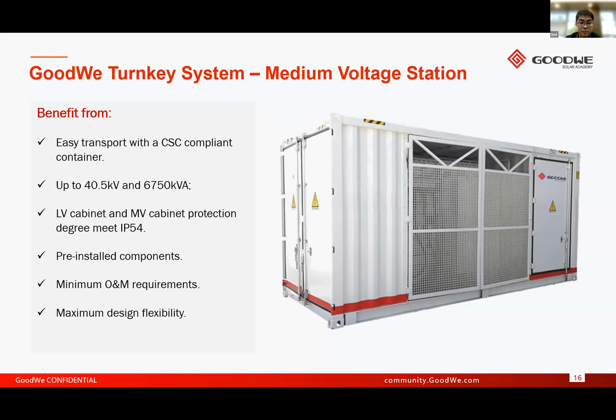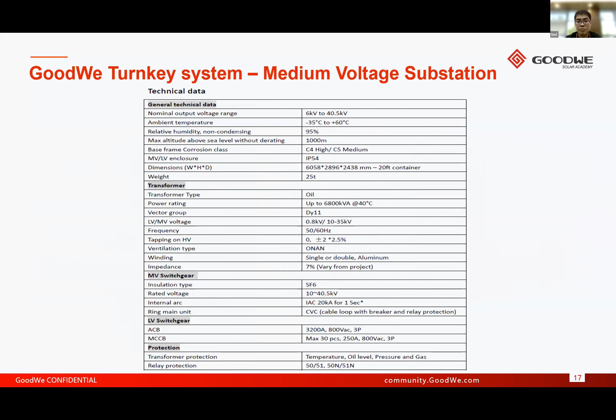As you can see from our data sheet, the maximum power rating we can now reach is 6,800 kVA. The low voltage side can support up to 30 pieces of MCCB to connect with. We've also heard from clients that they may have a solar array of less than 3 megawatts, so we can customize the power rating to meet your requirement.